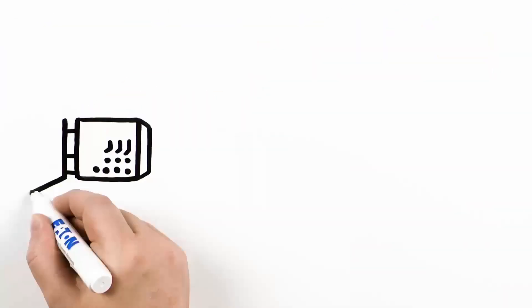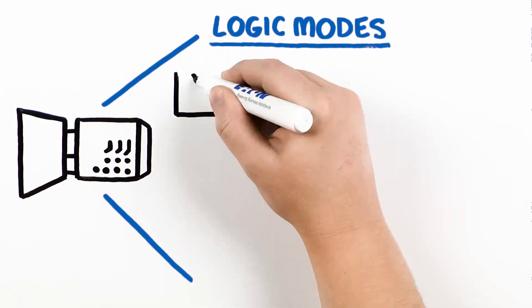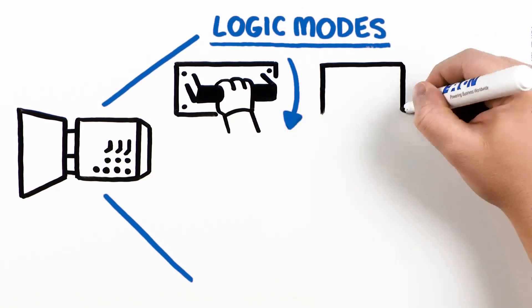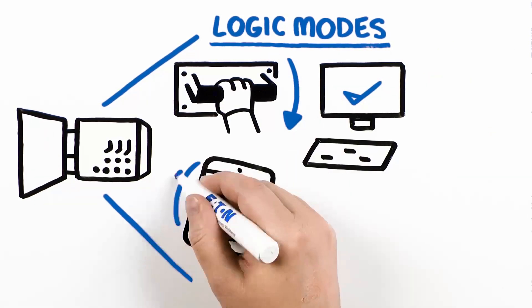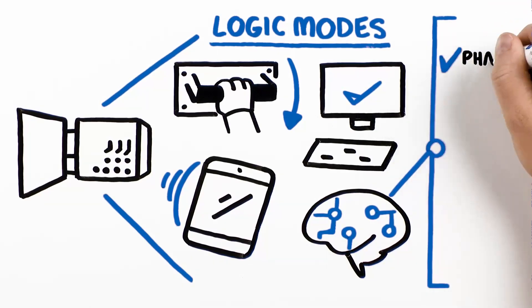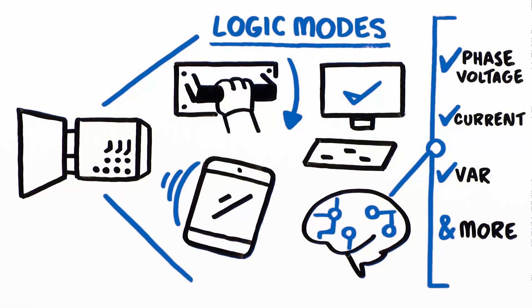Eaton's capacitor controllers offer multiple logic modes. These can include local control, often used for inspection and maintenance purposes, time-based programmable schedule switches, remote control, and smart logic utilizing various sensor readings of phase voltage and current, VAR and more to make switch decisions.